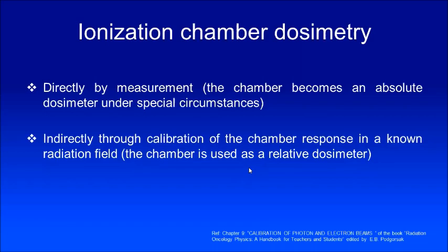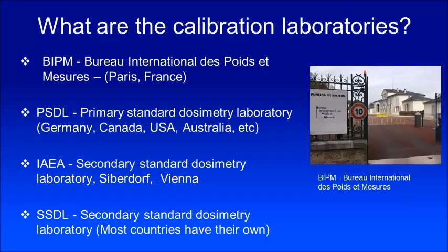Your ion chamber could either be an absolute dosimeter or a relative dosimeter — if it gives you directly the dose, then it is an absolute dosimeter; if it requires a calibration factor, then it is a relative dosimeter. How do you get these calibration factors? There are standard laboratories that can provide you the calibration factors under standard conditions. One is the BIPM in Paris, which is a standard laboratory not only for ion chamber measurement but for everything — for length, weight, and many other parameters.